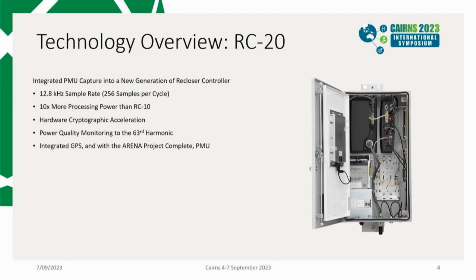And so the integration of the GPS system, and with the completion of the ARENA project, the integration of the PMU based on that GPS capability and the improved sample rate, gave us the hardware fundamentals. What this meant was that for some of our partners, they could use existing high voltage assets and simply replace the controller in order to gather the PMU data from their existing network base. And since that was not a high voltage operation, it could be significantly more cost effective to gather this information out in the field.